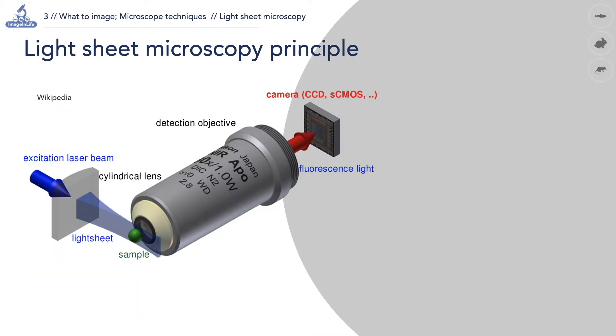This schematic shows that the light sheet is formed by a cylindrical lens and it travels to the sample from the side. The emitted light is collected by a second objective orthogonal to the light sheet. As a consequence of this geometry, all the photons from the illuminated plane are collected simultaneously. An ultrafast and sensitive camera detects at once all the photons from the illuminated plane.